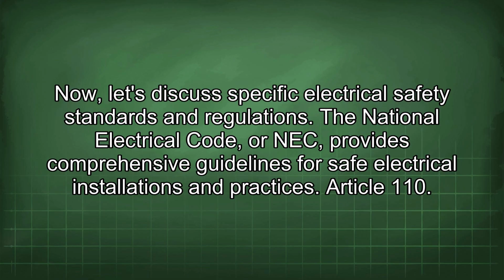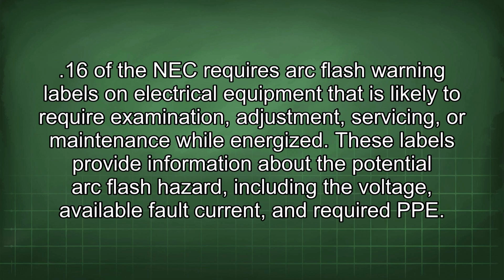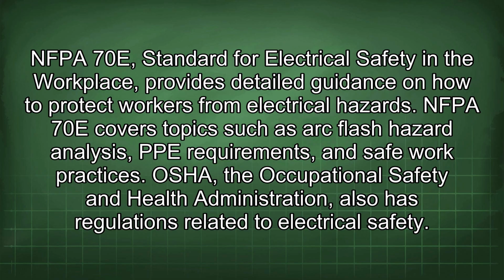Article 110.16 of the NEC requires arc flash warning labels on electrical equipment that is likely to require examination, adjustment, servicing, or maintenance while energized. These labels provide information about the potential arc flash hazard, including the voltage, available fault current, and required PPE.